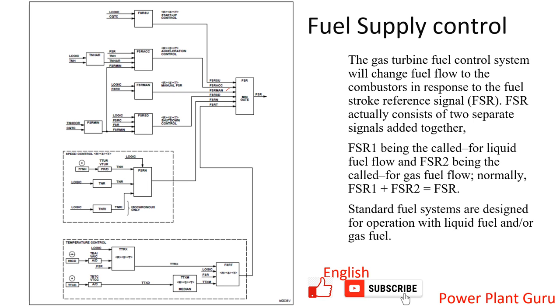Then FSR SD, that is shutdown FSR. Let's say you give a shutdown command at any particular load, then whatever fuel flow the machine should follow, that should be FSR SD. Then FSRN which normally comes in control when you operate this machine on synchronous mode. This is particularly for synchronous mode only, otherwise if you operate machine on droop then this will not be applicable. Then there is FSR T which is fuel stroke reference when machine is operating in temperature control mode, so you have hit the highest exhaust temperature limit that is limiting your machine loading.